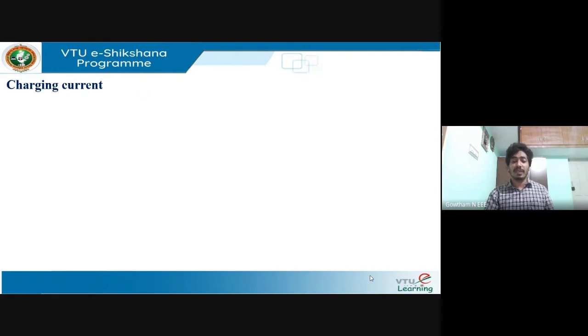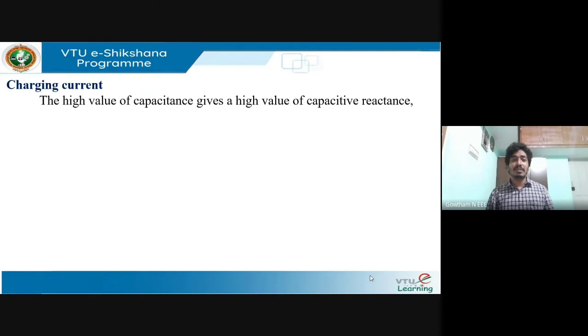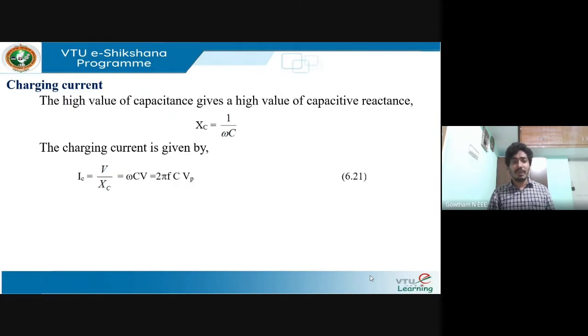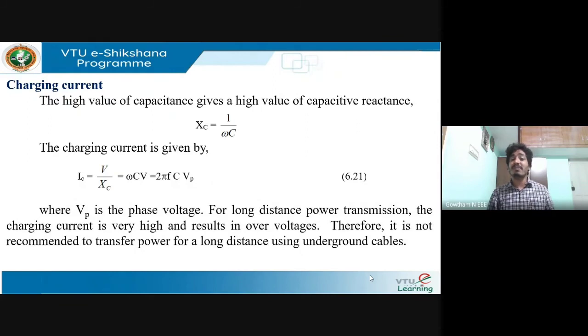A high value of capacitance gives a high value of capacitive reactance. The capacitive reactance X_C = 1/(2πfC) = 1/(ωC). The charging current is I_C = V/X_C = ωCV, giving I_C = 2πf C V_p, where V_p is the phase voltage. For long-distance power transmission, the charging current is very high and results in overvoltages; therefore underground cables are usually not recommended for long-distance power transmission.